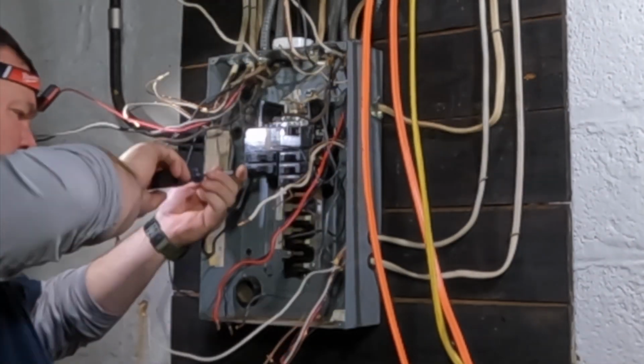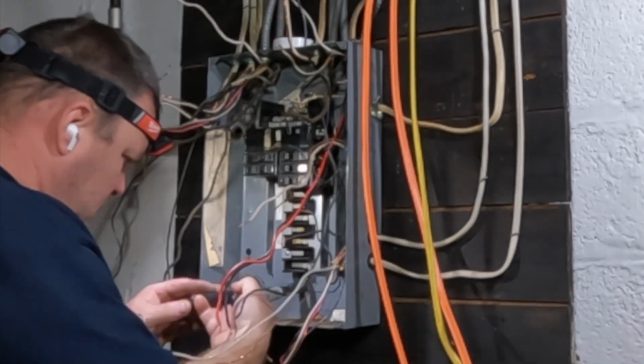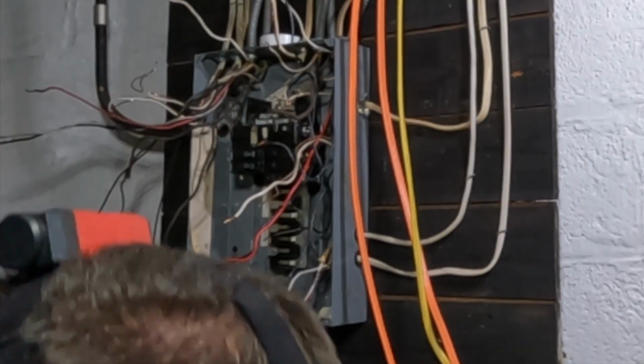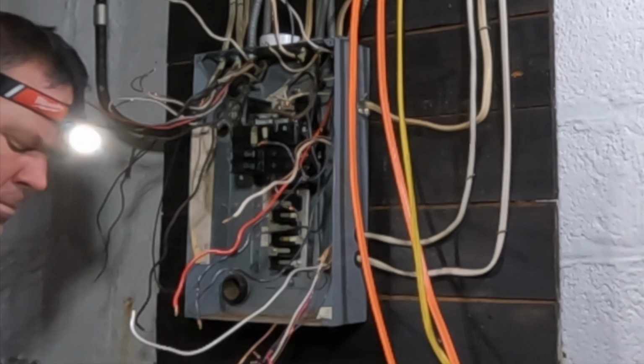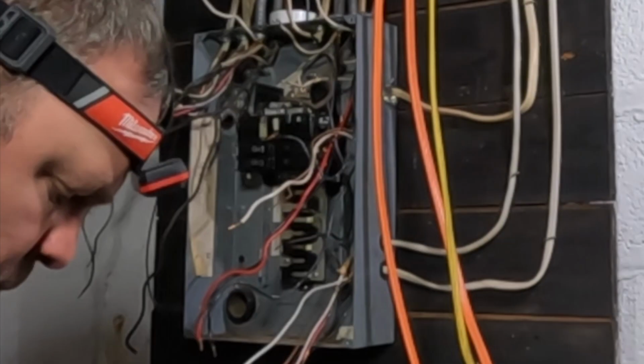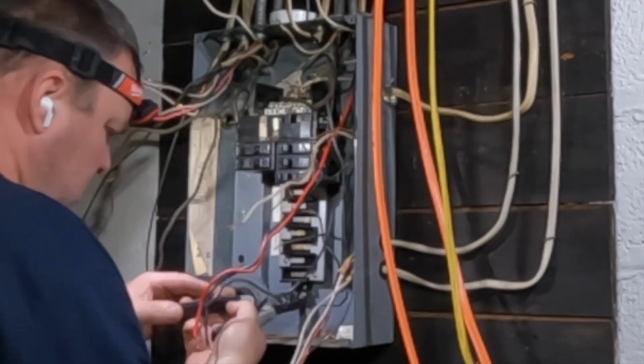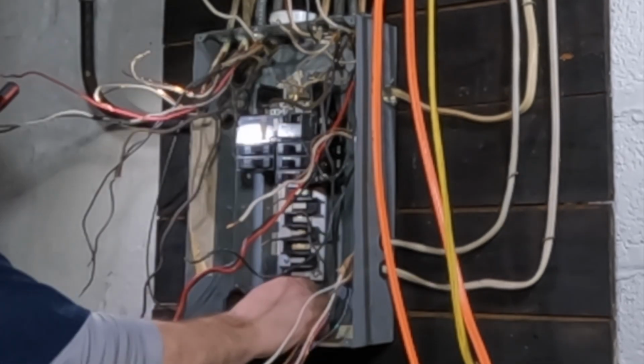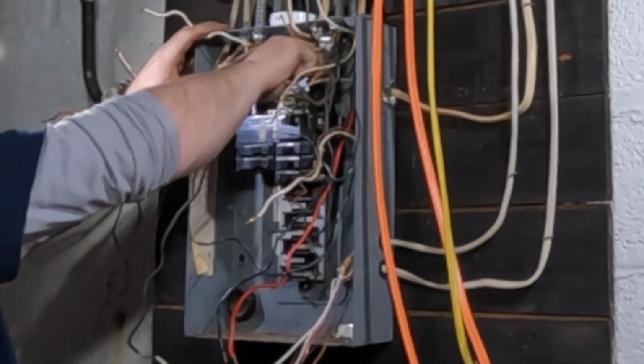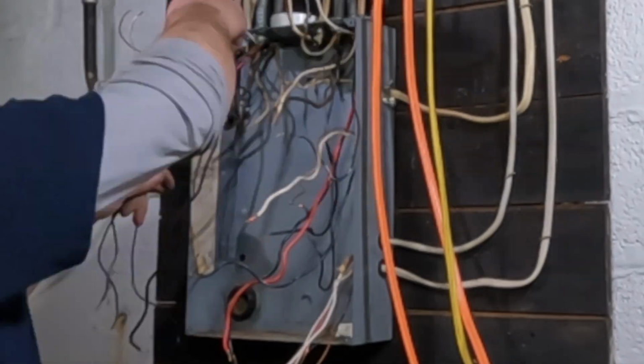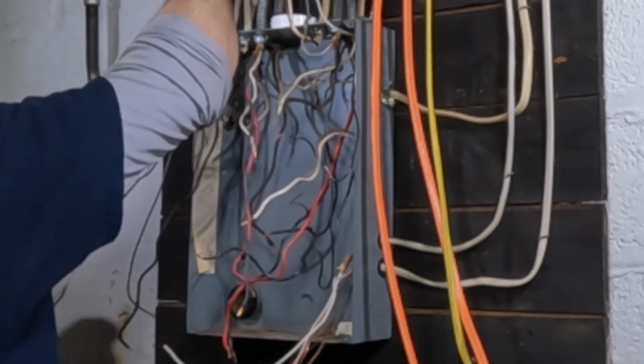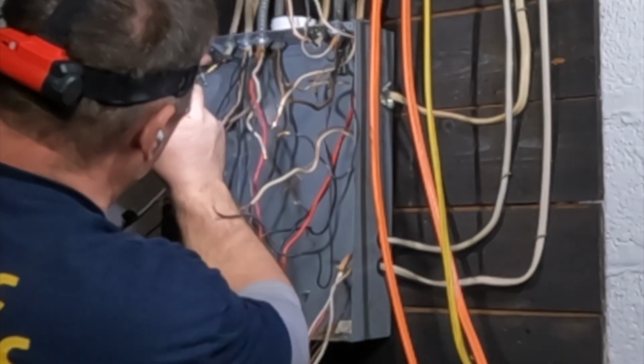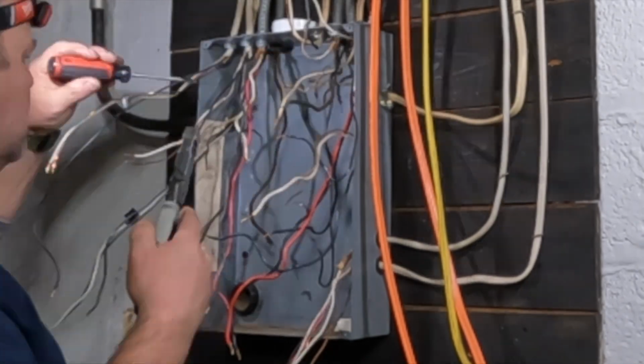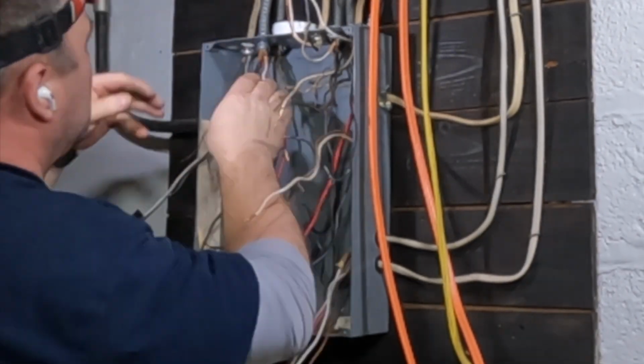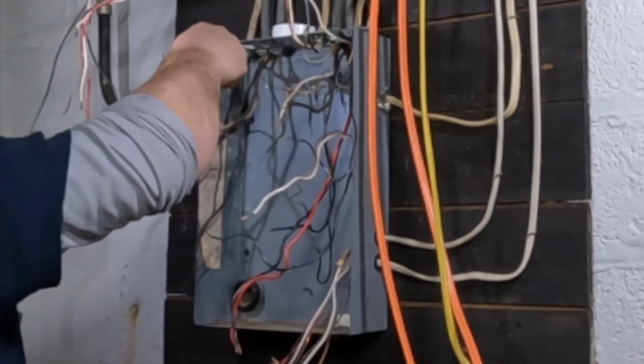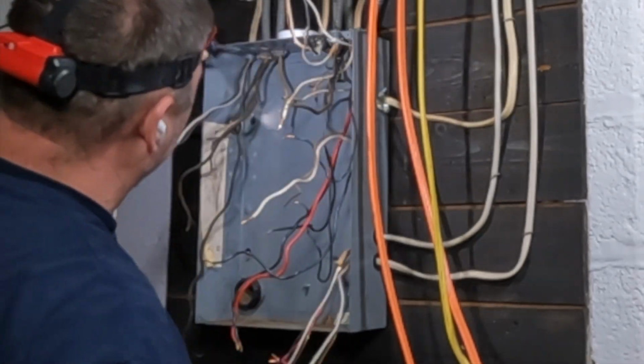As you can see, this panel was full. There was 1 space left, and we were adding at least 5 circuits here. 2 of them were going to be 240 volt circuits, which takes up 4 spaces, and another single pole 20 amp circuit, which takes up 1 space. And then, of course, we have to put in the surge protection, which takes up another 2 spaces. So 7 new spaces that we use in a new panel for the 200 amp service, 40 circuit, the 40 space 80 circuit panel we're going to be putting in.